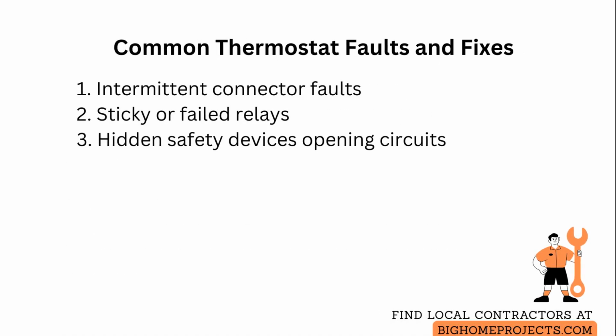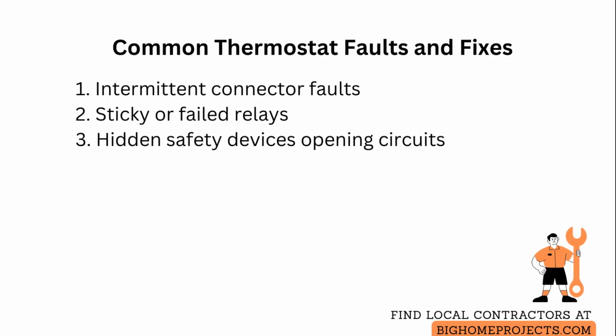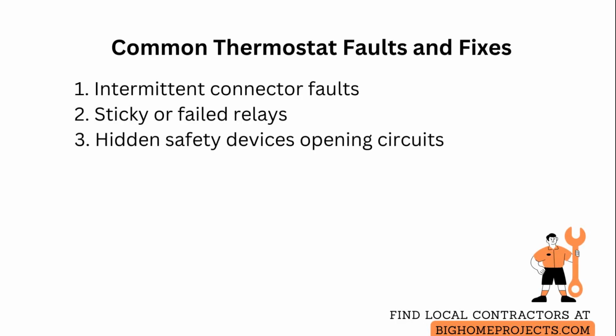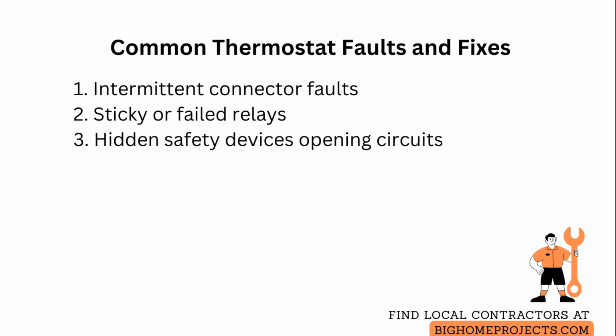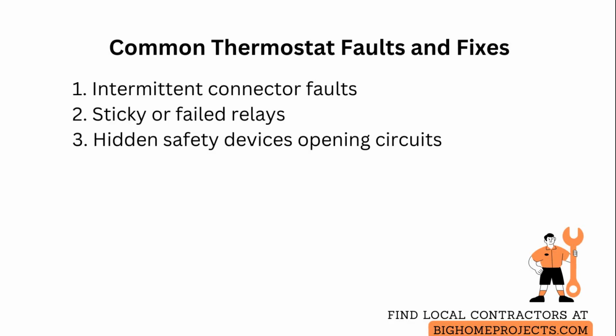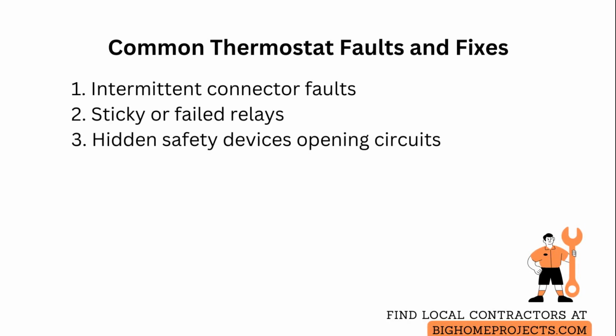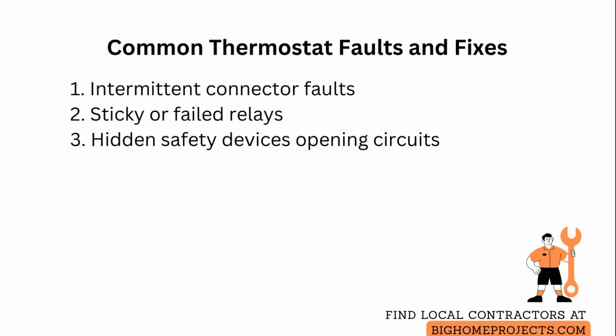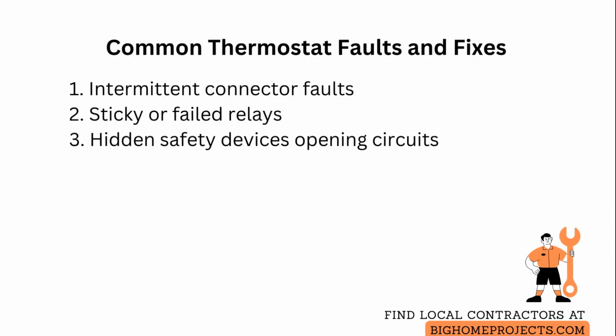The three most common issues when thermostat wiring and the main board appear fine are intermittent connector faults, sticky or failed relays, and hidden safety devices that open control circuits. For intermittent connectors, the fix is to replace or reterminate the connector and use dielectric grease or heat shrink to protect against moisture and corrosion. For relays that stick or have degraded contacts, replace the relay with the exact coil voltage and contact rating and verify operation under load rather than relying on visual inspection alone.